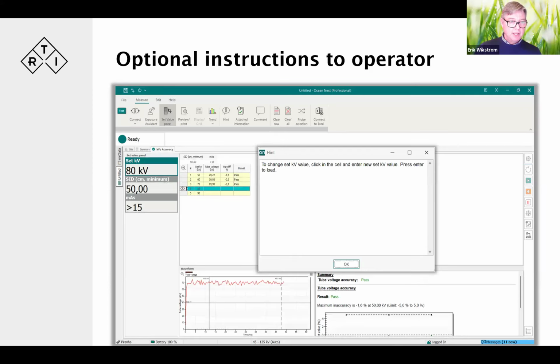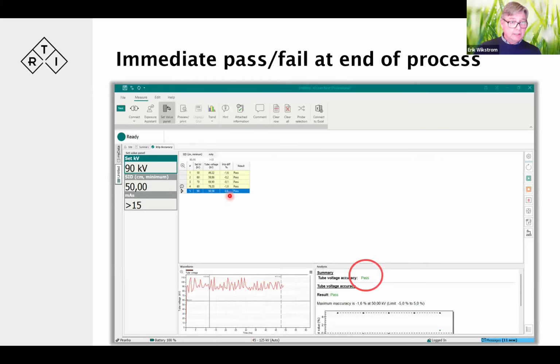And we continue with doing 70, and as we hit 80 kV, if we wanted additional information, a hint can pop up and say that, okay, for this one we need to add a copper filter, or a different technique, different calibration, focal spot, something that you need a reminder of. Again, we need to click OK to move beyond that point. And when we've finished everything according to this schedule, this test, we see that all lights are green. We have a pass, and that's what we're looking at.